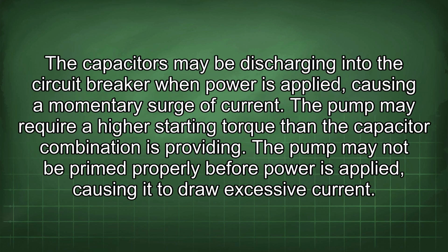The capacitors may be discharging into the circuit breaker when power is applied, causing a momentary surge of current. The pump may require a higher starting torque than the capacitor combination is providing. The pump may not be primed properly before power is applied, causing it to draw excessive current.